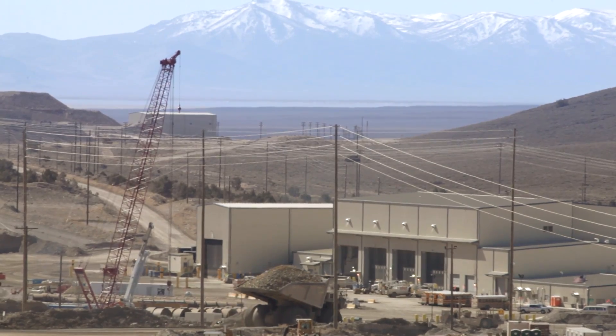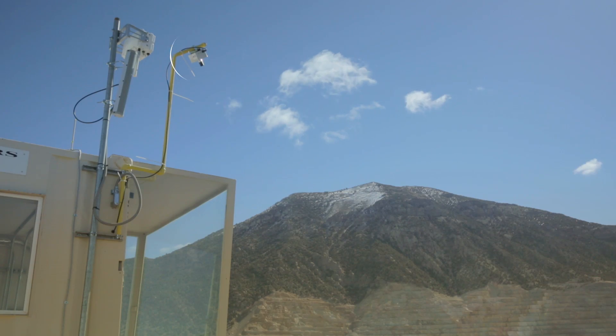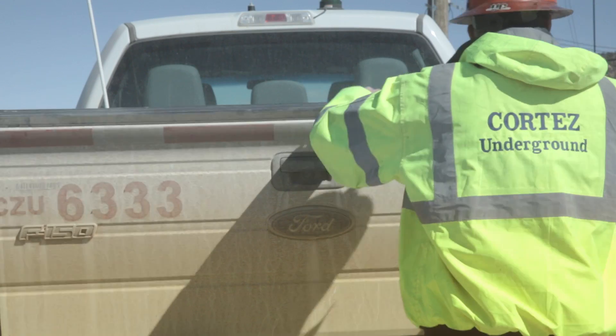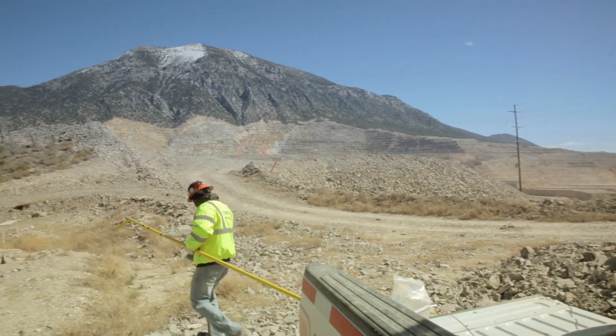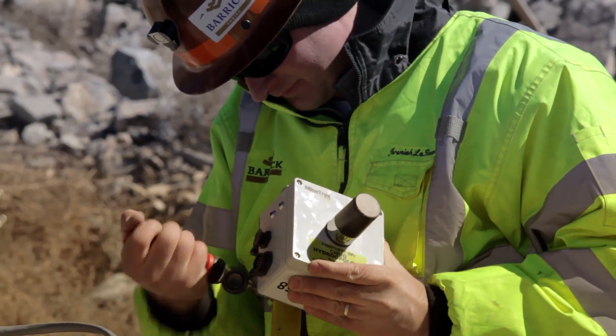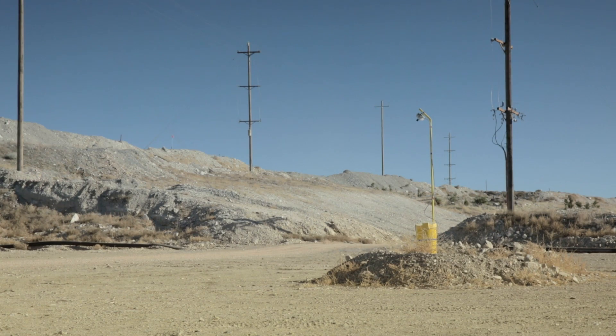On surface, it's just as simple. The Ethernet gateway is connected to the network inside a surface building. The first network node is installed with a 20-foot cable and mounted on the outside of the building. All other nodes are installed at each piezometer location for simple data collection, especially where locations are hard to access by ground. The wireless RTU is typically mounted on top of a pole and connected to a 12-foot cable that links it to the piezometer in the well. Up to four vibrating wire piezometers can be monitored with one wireless RTU.